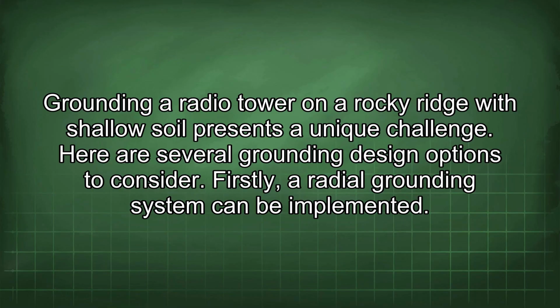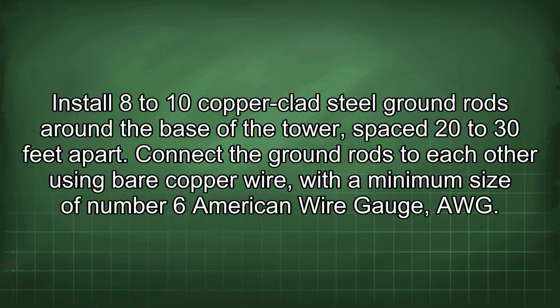Grounding a radio tower on a rocky ridge with shallow soil presents a unique challenge. Here are several grounding design options to consider. Firstly, a radial grounding system can be implemented. Install 8 to 10 copper-clad steel ground rods around the base of the tower, spaced 20 to 30 feet apart.